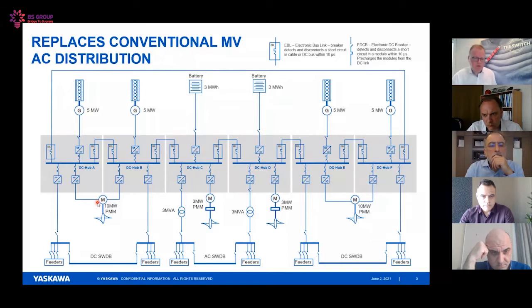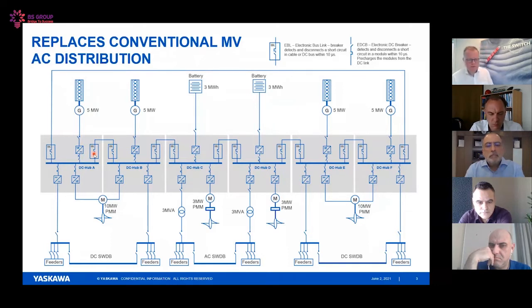The main point here is the electronic bus link. That's the one that makes this possible, because it reacts so fast in case of a short circuit on the cable - it will disconnect everything within 10 microseconds. That is much, much faster than any fuse or breaker can do.